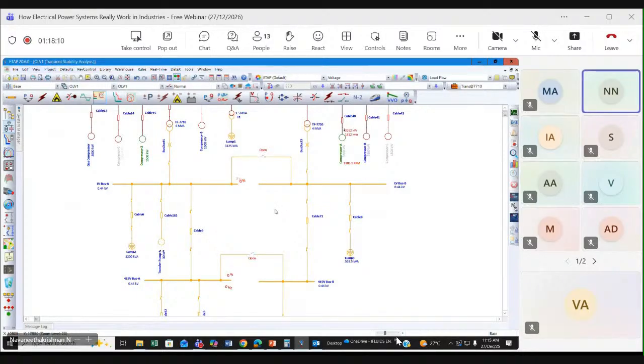Does anyone know whether the transformer rating is for input or output? Anyone, lift your hand. Is the transformer designed for input or output capacity? Okay, the transformer is designed for output rated capacity as per IEEE, and for input capacity as per IEC. Because the loss in a static machine is very little, even if you overload by 5%, the transformer is not going to have a problem for a short time. That is how it is. But you should not design transformers neck to neck.